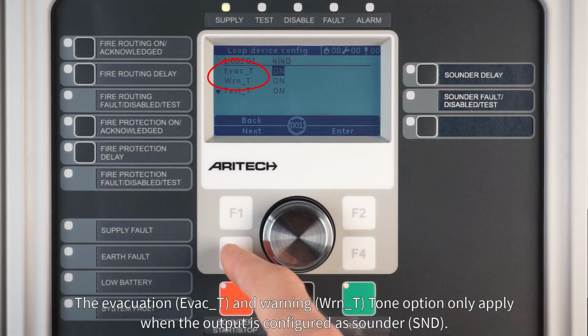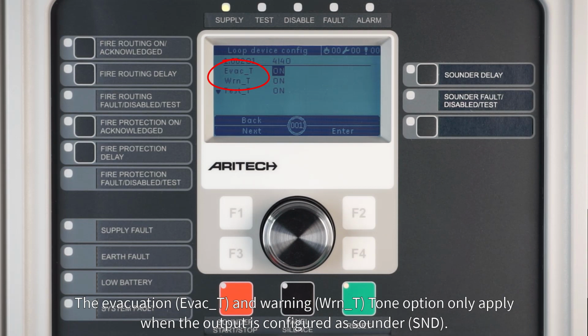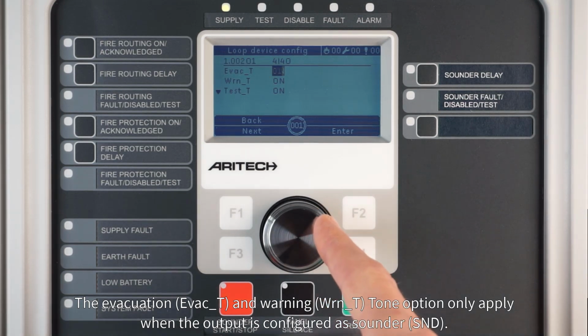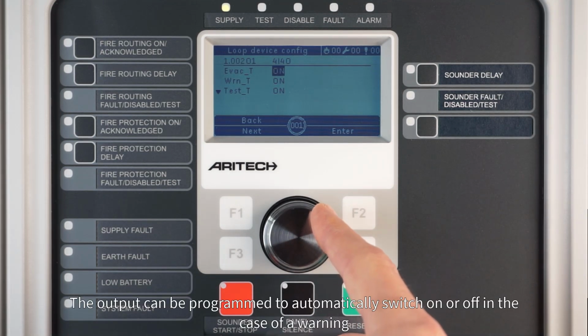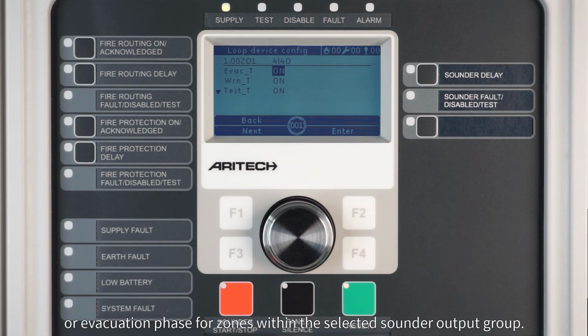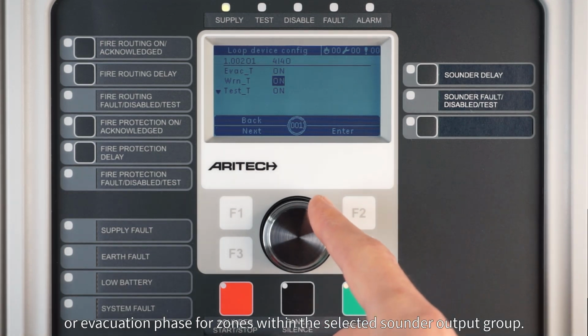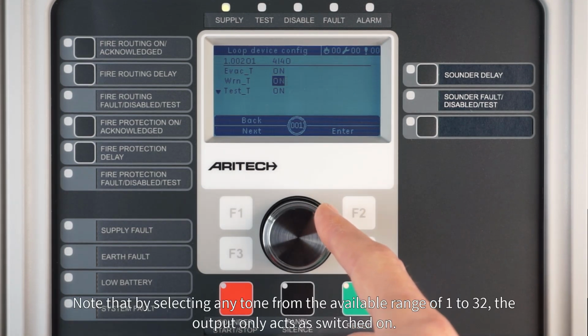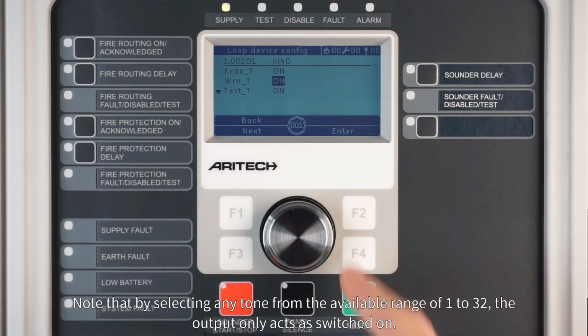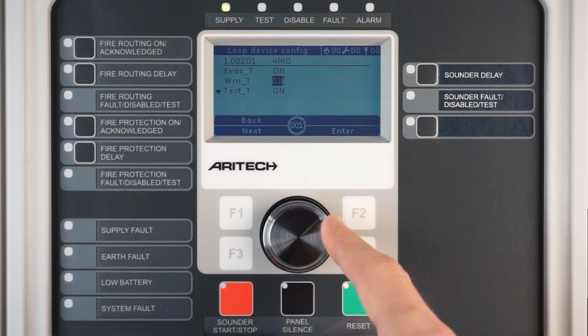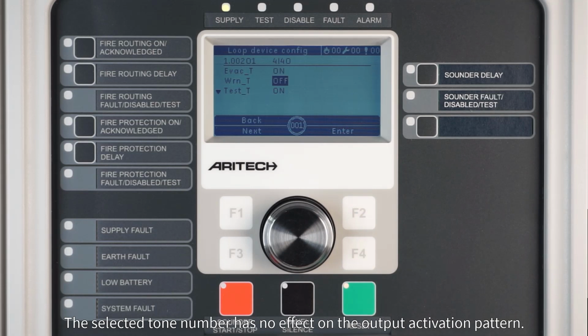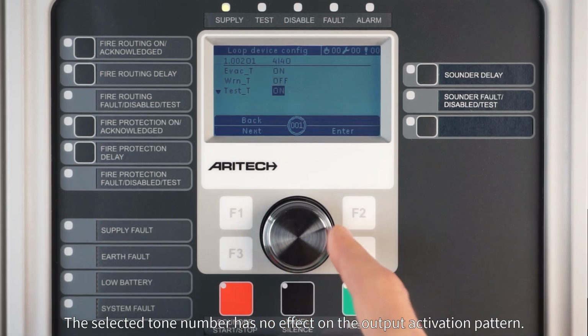The evacuation and warning tone options only apply when the output is configured as sounder. The output can be programmed to automatically switch on or off in the case of a warning, or evacuation phase for zones, within the selected sounder output group. Note that by selecting any tone from the available range of 1 to 32, the output only acts as switched on. The selected tone number has no effect on the output activation pattern.